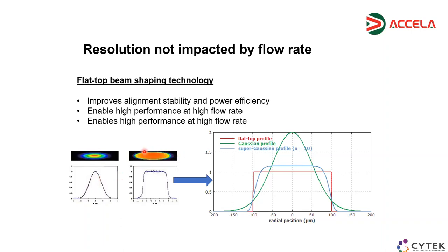But what about if we modify slightly the geometry of the laser, applying this flat top correction? This is what the engineers at Cytek decided to do. They apply a lens system in front of the laser to increase the exposition surface and keep good intensity across a larger surface.